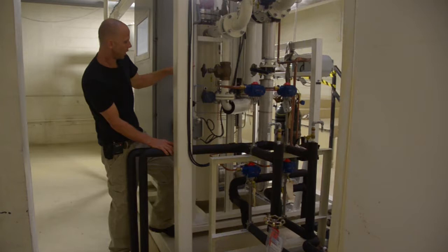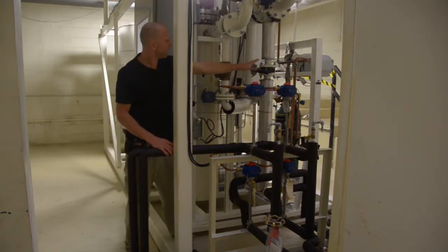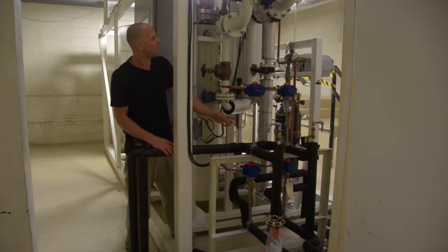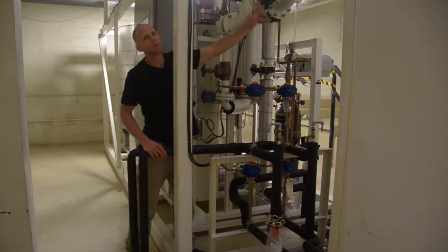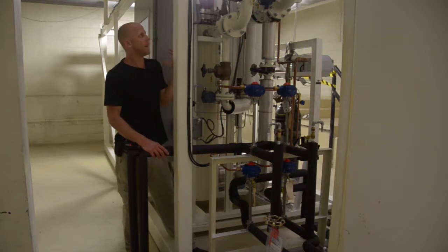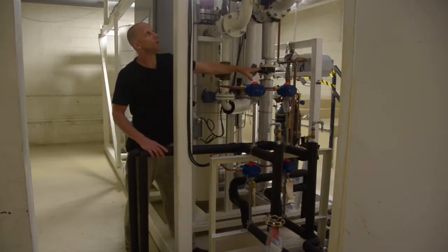The other line which you will see, which may cause some confusion at first, is this line here. And this line is a line that we can use only for thawing the plant or deriming the plant, and it allows us to take hot air from the heater with a modified set point so that it's not too hot, and to put that air into the process air line so we can put hot air through our column. Okay. You can also thaw and derime the plant without using hot air, because the air that's moving through the online bed is so dry that you don't really need heat to thaw the plant. But if you would like to use that function, there is a hot thaw function, and this is the valve that you would use to do that.